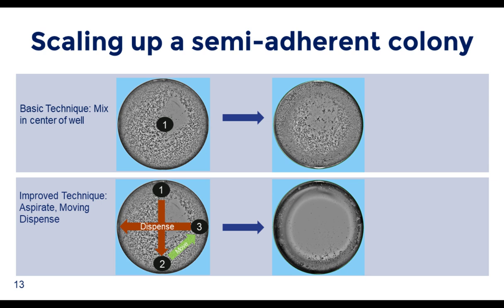For larger wells, a moving dispense technique can be utilized, emulating what a person does. Developed with extensive support from a Beckman Coulter expert, mixes are performed at edge locations with dispenses occurring as the tip moves across the well, dislodging cells. For example: mixing at location 1, aspirating at location 1, then dispensing while moving from location 1 to location 2. Key optimization questions include: how much volume to mix, how fast to mix without losing viability, and what pattern to use. Performing the final aspiration close to the edge and bottom of the well was found sufficient — no need to tilt the plate.